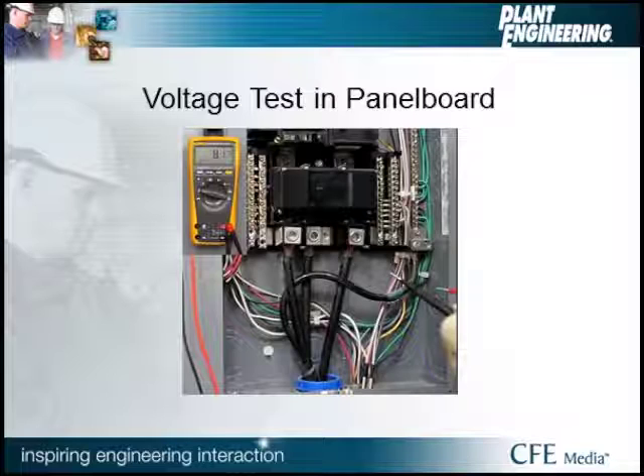All right, again, I want to point out that it's important when we're doing this type of test that we always make contact with the grounded conductor or the neutral first, and then we make our contacts with the various ungrounded conductors. This is because the equipment would be fully energized once we make that contact.